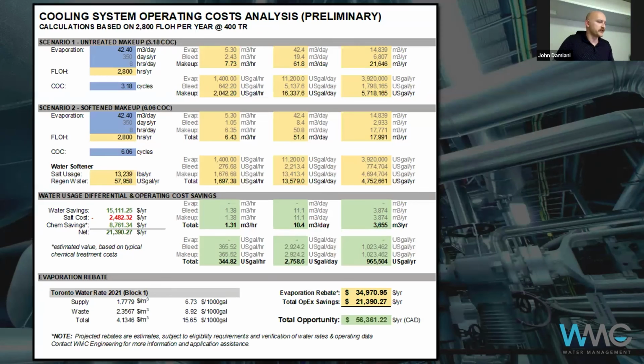Just to finish off quickly, with a couple minutes left: operating cost analysis gets into the engineering side of things. Setting aside the numbers, it's really just breaking down two scenarios—untreated makeup, in this case achieving 3.18 cycles safely, compared to softened makeup, which nearly doubles the cycles of concentration. Evaporation stays fixed, and this calculation shows what the water usage ends up being for a certain load.